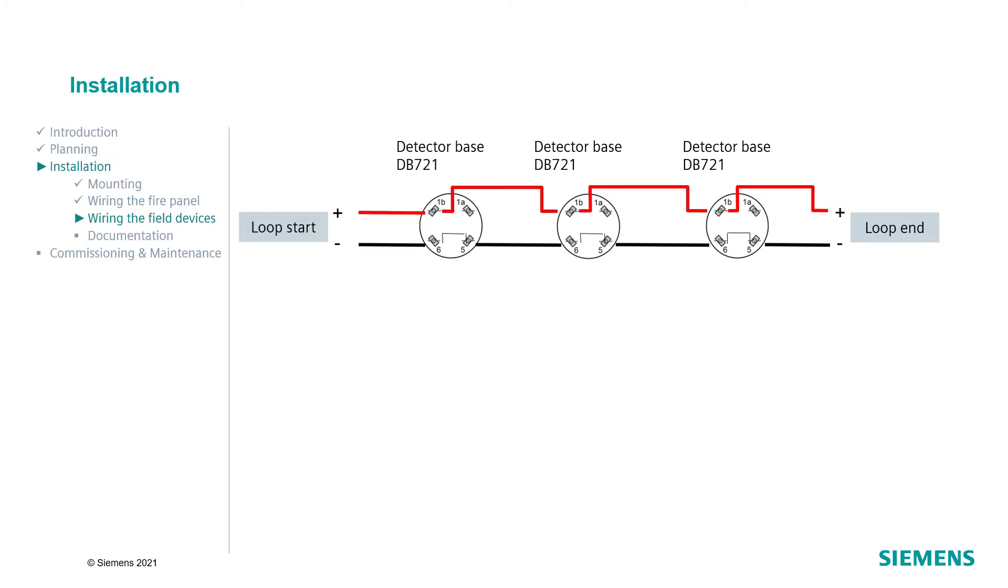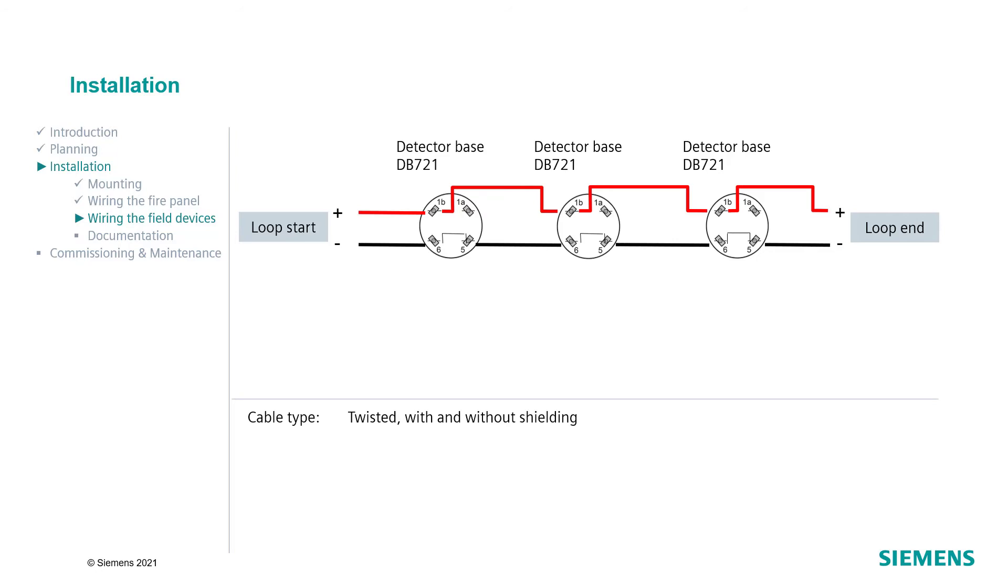Next, let's take a look at the connection of the field devices. In order to wire the CNET, use a twisted pair cable with or without shielding. We recommend using unshielded cables as it simplifies the installation and there is no need to remove the shielding. Please make sure that the cable type used complies with local regulations.